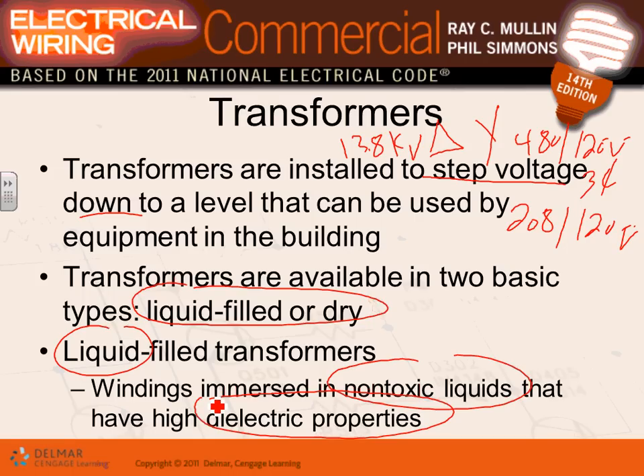And that's why if you have an oil-filled transformer, you can load that one. You can force it. Really, it's cool. It has good cooling on it. Okay. So the liquid, what does it do? It essentially insulates. This is the key point, guys. It insulates the high voltage winding from the low voltage winding and helps in the cooling of the transformer.